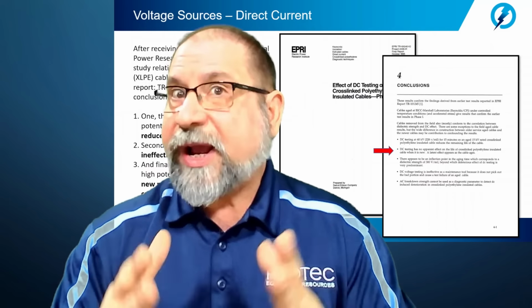Reapply your DC high potential test. Just see how high you go to get that cable to break over, if you get it to break over. And that is why we say that the DC testing is ineffective as a maintenance tool. It is ineffective in identifying and uncovering all of the type of defects that we would get in a service-aged cable, or a cable that has been in use.